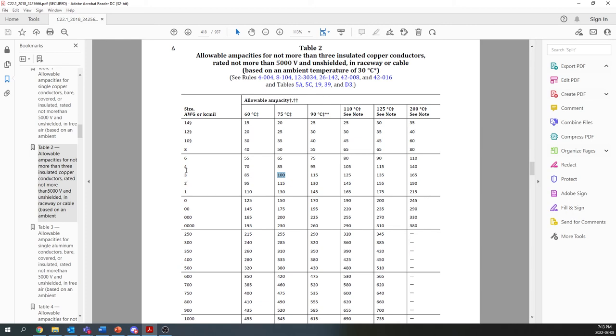But we're forced to do that because, again, we have to ensure that we're doing things safely and taking into account the temperature rise that is going to occur in the wiring, because there are all these wires close together. So we'd have to apply the same process to the 65 amp circuit. So 65 times 0.8 is 47.32 — wait, that's 65 times 0.91 times 0.8. So now we actually have to install a number 4 for that one. Yeah, and we're fine for that. It gives us 61 amps.